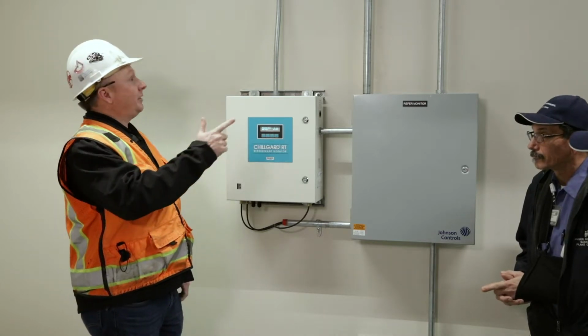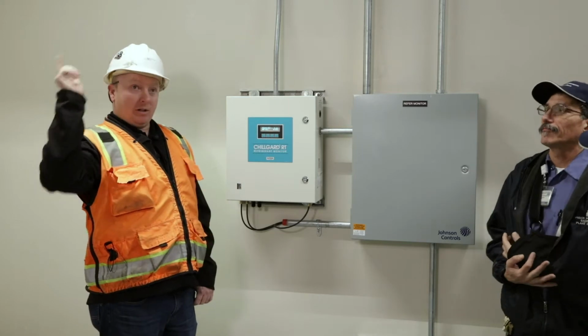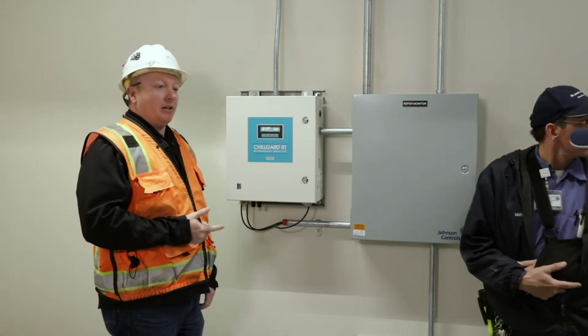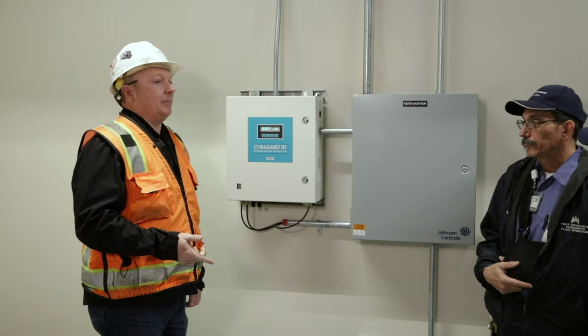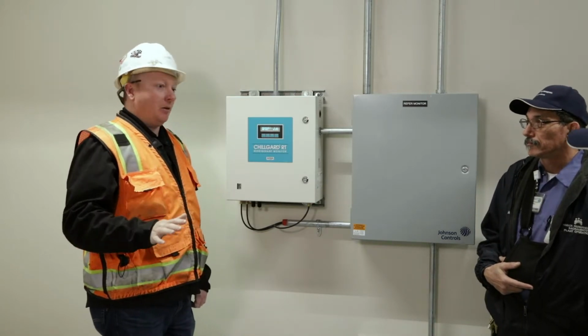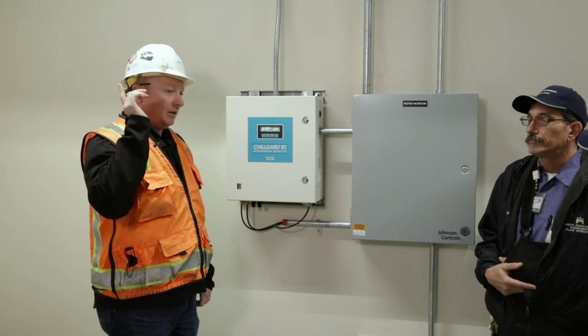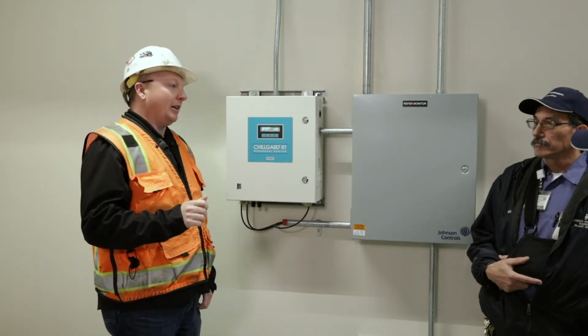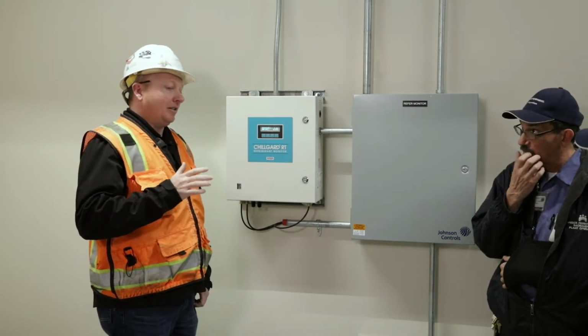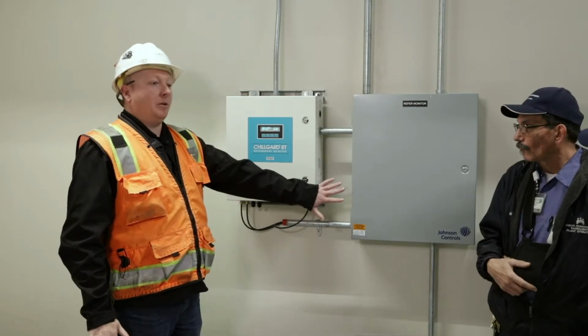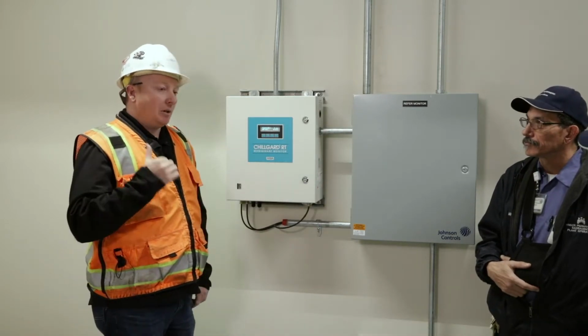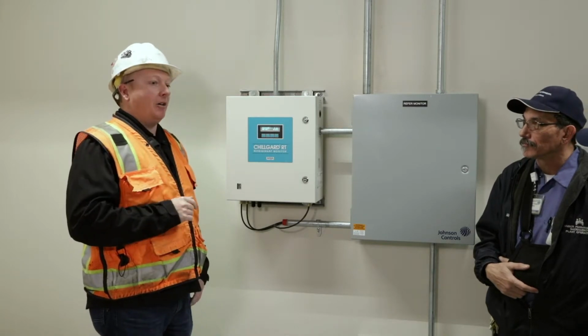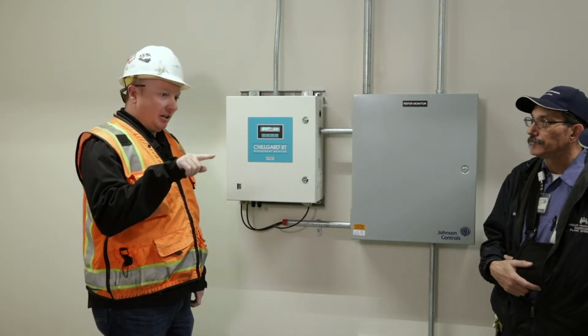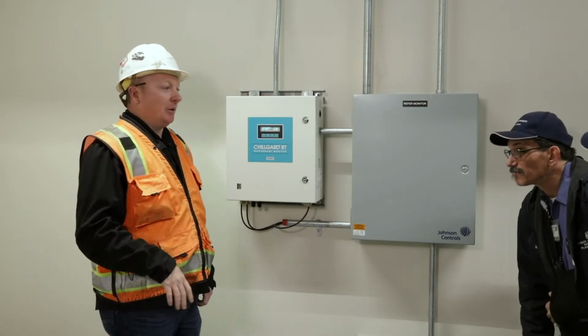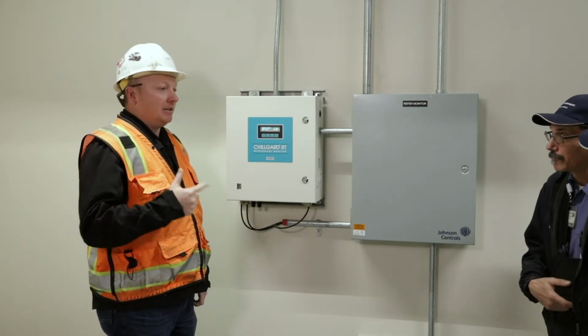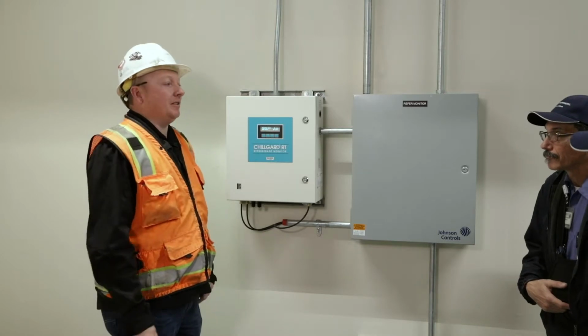The horn strobes are gonna go off. They're all around here, and there's one outside at each door, and you're gonna get an alarm on your building management system. It's not gonna shut down the machines. It's just going to start the fan and all the lights and sirens. If you do the break glass for the emergency shutdown, it's gonna shut everything down just like this thing would do automatically. These ones are break glass push button style switches. So you break the glass and you push the button in, and it's a maintained switch. So when you push it in, it just stays there until you push it again and it releases.